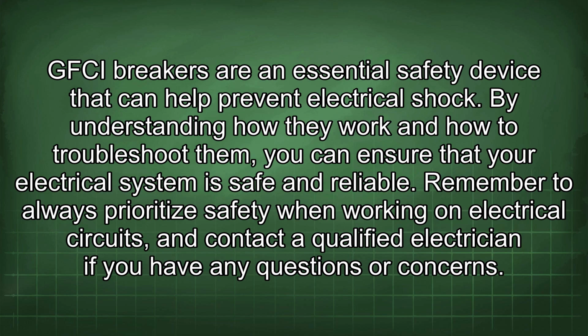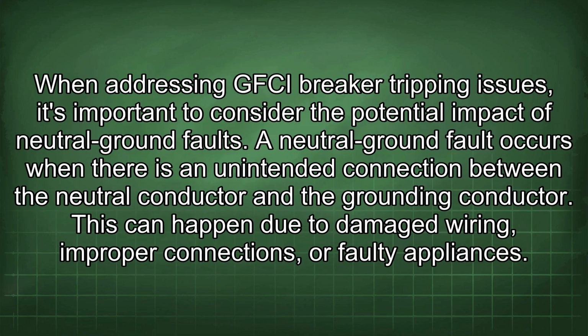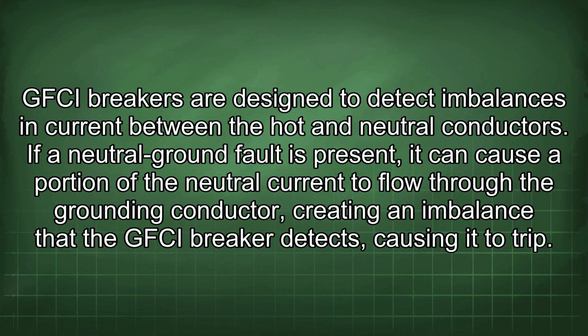When addressing GFCI breaker tripping issues, it's important to consider the potential impact of neutral ground faults. A neutral ground fault occurs when there is an unintended connection between the neutral conductor and the grounding conductor. This can happen due to damaged wiring, improper connections, or faulty appliances. GFCI breakers are designed to detect imbalances in current between the hot and neutral conductors. If a neutral ground fault is present, it can cause a portion of the neutral current to flow through the grounding conductor, creating an imbalance that the GFCI breaker detects, causing it to trip.